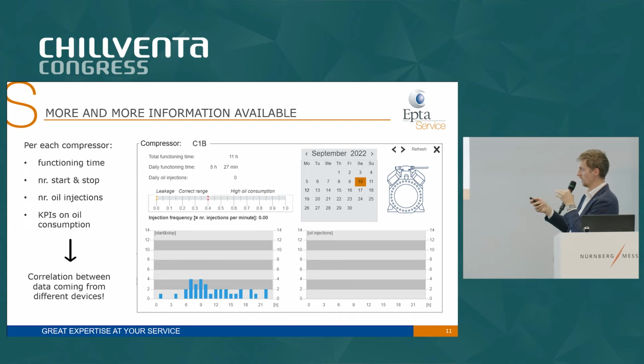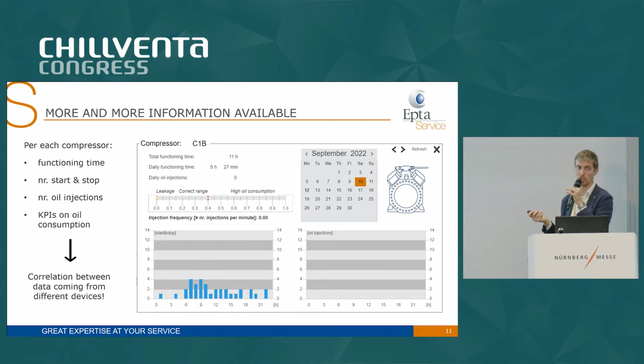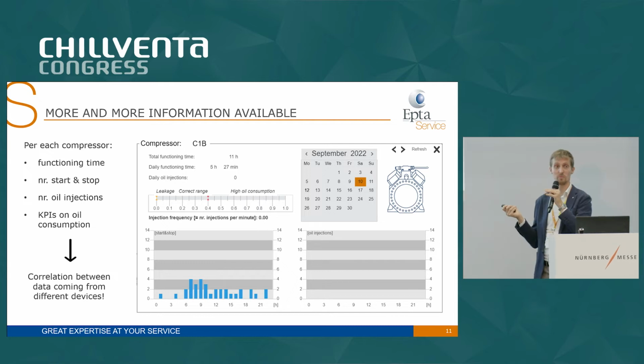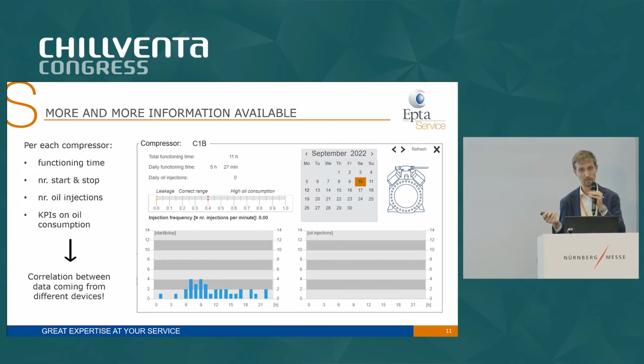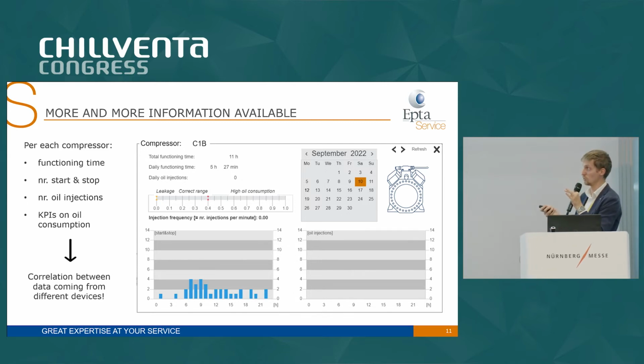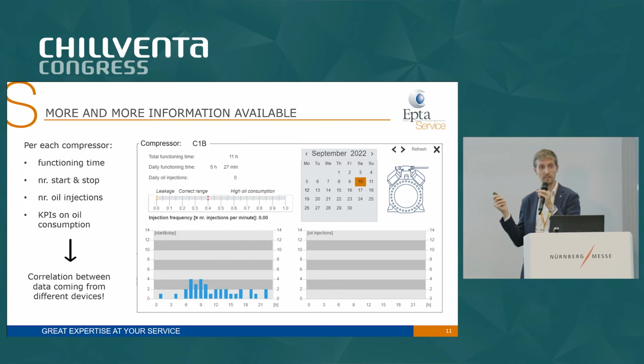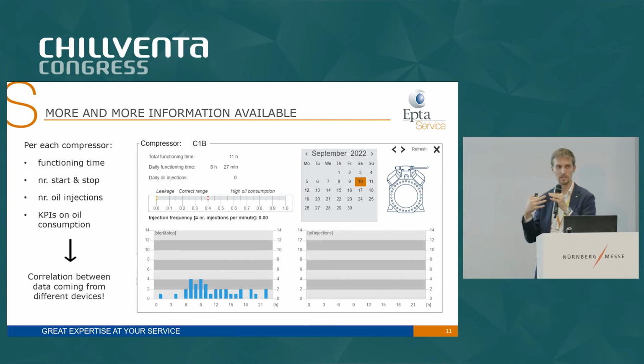For instance, here you can see the number of starts and stops of the compressor of this specific day, hour by hour. And close by, you have the same graph showing you the number of injections per hour of that compressor. Here you see 0. Probably the system was running in subcritical. Usually in subcritical, the consumption of oil is quite low, so no injection. So everything should be fine. But here, the point is we are merging data from different devices with this digital platform.